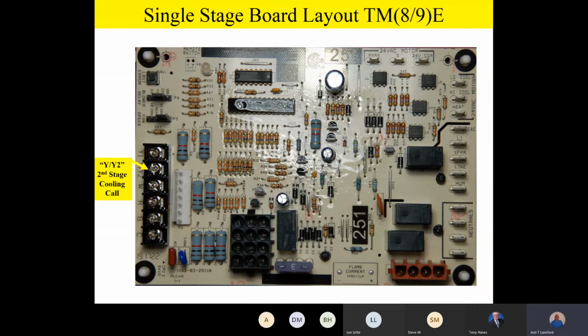Y/Y2 is to remind you that if you have it on a single stage product outside, you have to have 100% airflow inside. Let me say that again. If you have a single stage unit outside on a cooling call, Y, you just have a Y going outside, you want to make sure and use this Y/Y2 terminal. And the reason I'm stressing that is sometimes we've had some field calls and we've had some technical calls where the contractor said, well, you know, my airflow is not what it should be, and I've got a single stage unit outside, so they use the Y1 input.